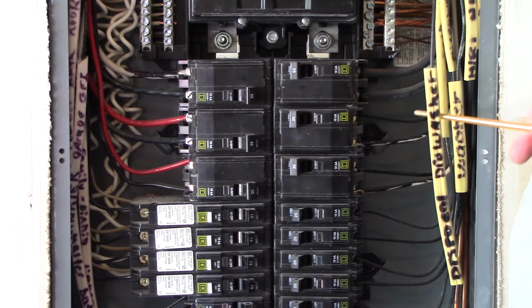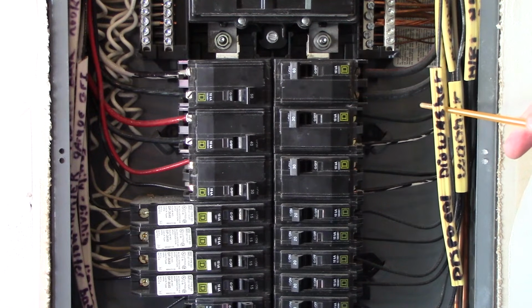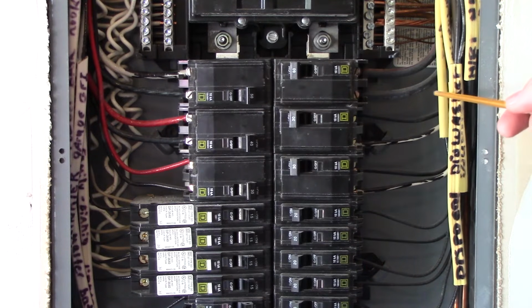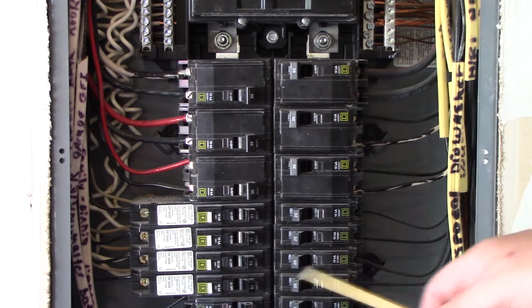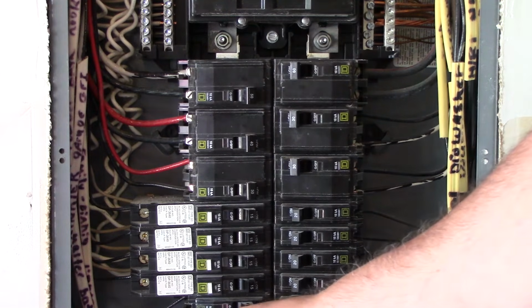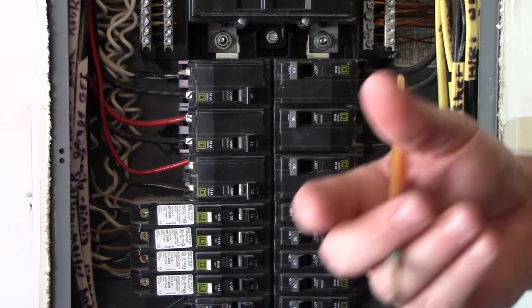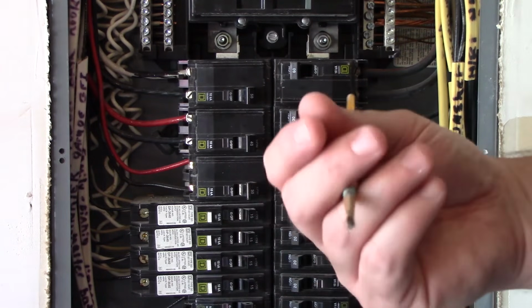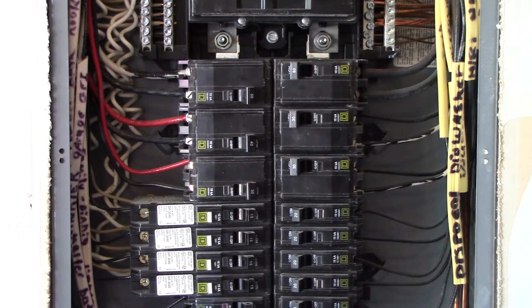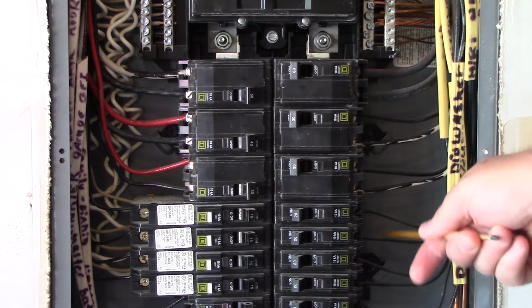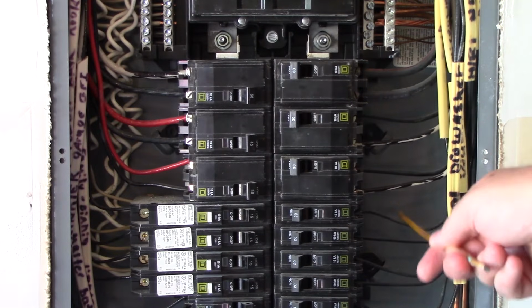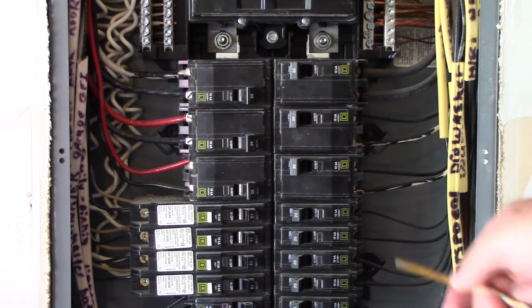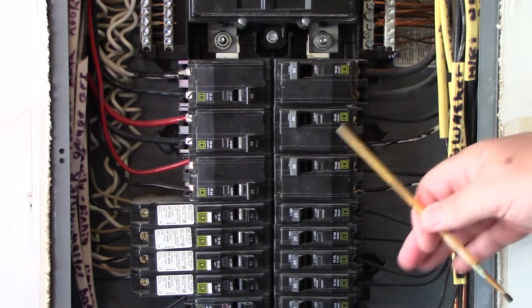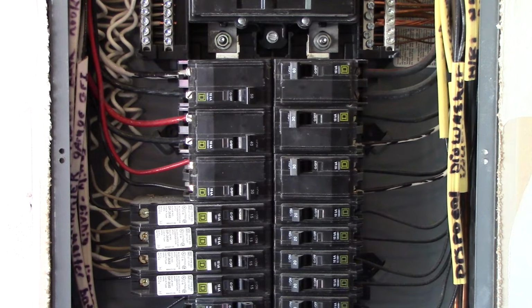And over here we got the yellow on here, which is indicative of a 12 gauge non-metallic sheath cable, but to verify we can see the contrasting sizes between the 14 and the 12. And if anybody's ever worked with 12 a lot in kitchens and dining rooms and what have you, you get to know really quickly what a 12 gauge looks like. So here, you can tell how stiff they are using a non-conductive probe. I kind of just touch them a little bit. I can tell what they are. So these are 12. So this looks like all of the breakers are terminated properly.